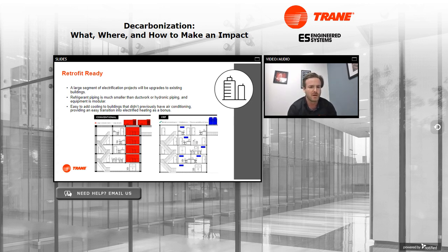You don't have to run ductwork into a building for VRF, just refrigerant piping. You don't need mechanical space for large equipment. VRF outdoor units are modular, so you can fit them where they fit, and you can use a variety of unit styles to place equipment wherever possible.